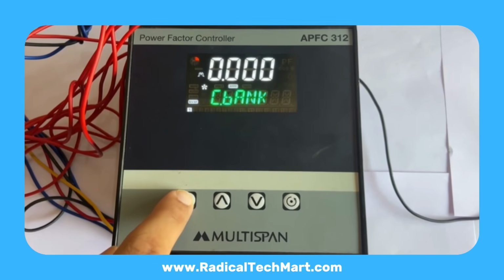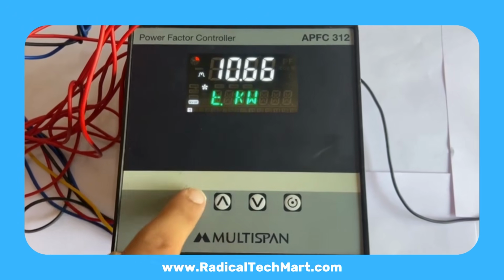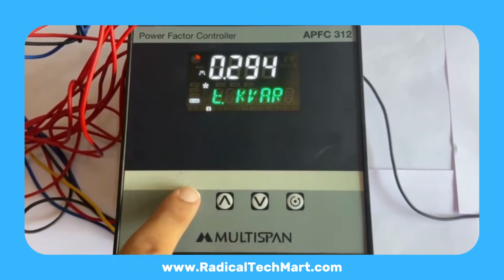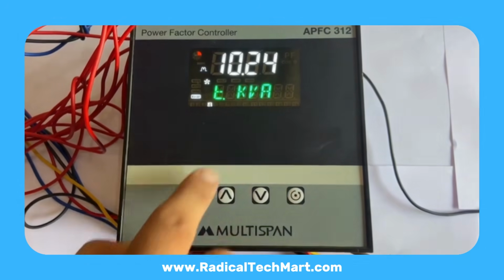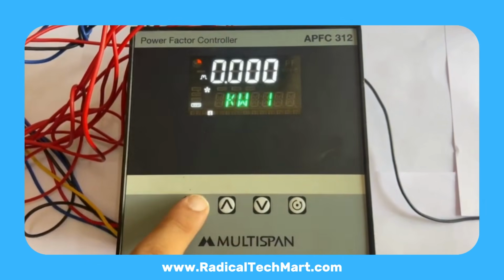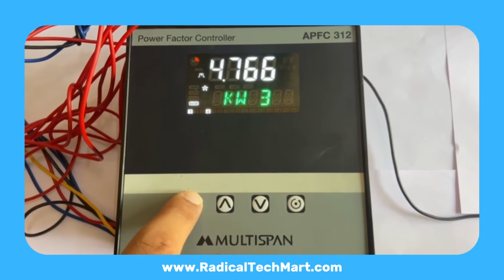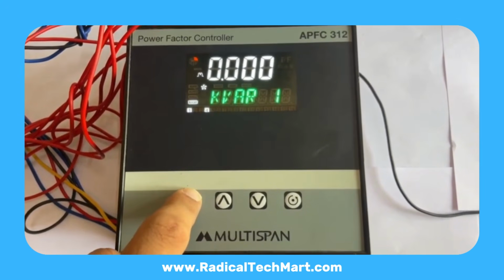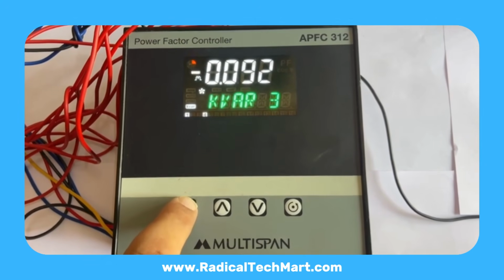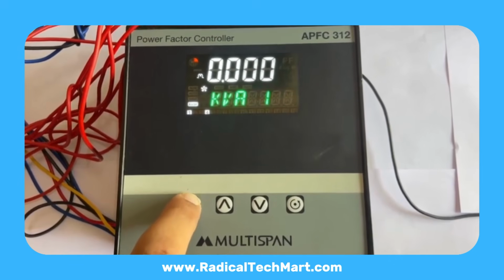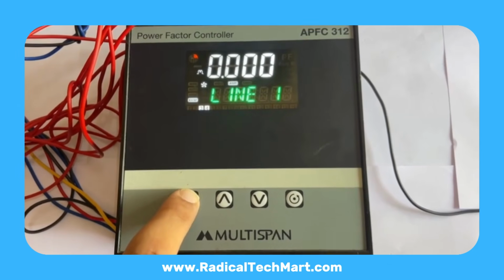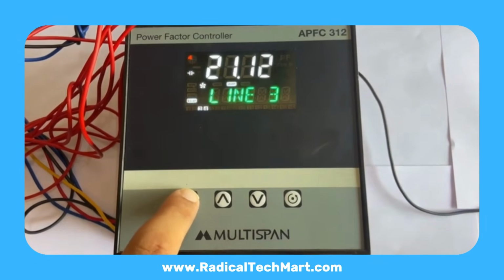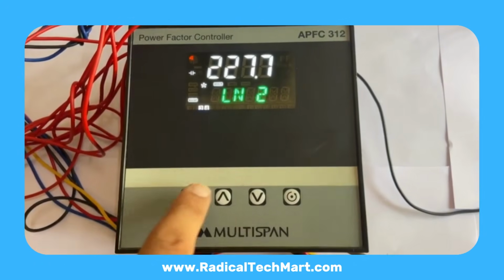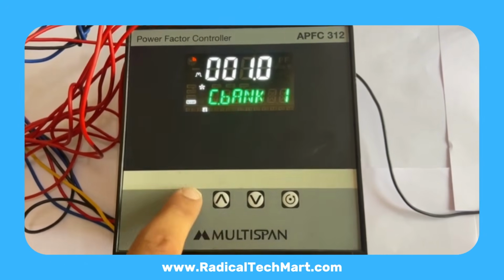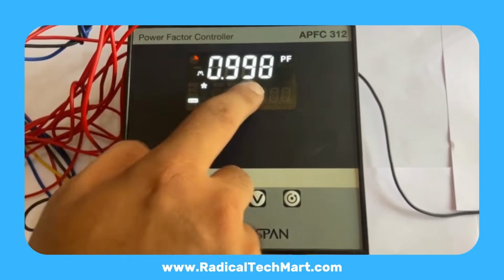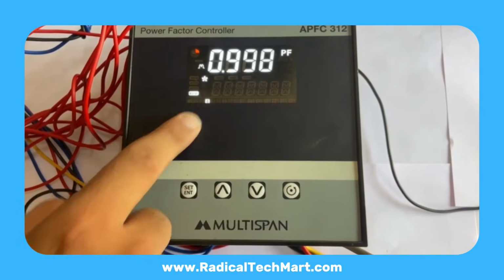Press set to continue. You can now monitor required kilovolt ampere reactive, capacitor bank on status, capacitor currents, total current, total kilovolt ampere reactive, apparent power, phase-wise current R, Y, B, phase-wise voltage, individual capacitor step status. Right now, the step 4 capacitor is on, and the relay shows 998 and the total capacitor bank value on the screen.